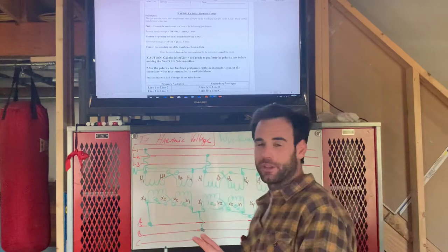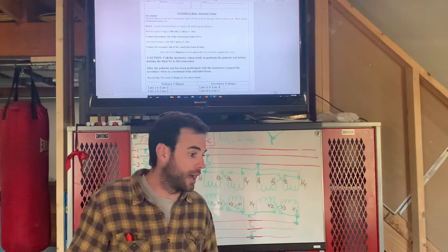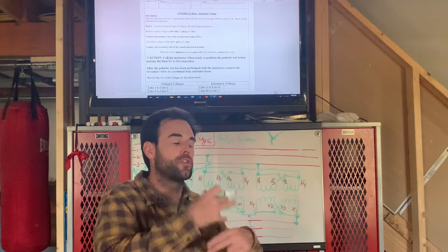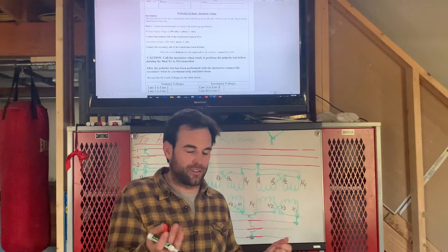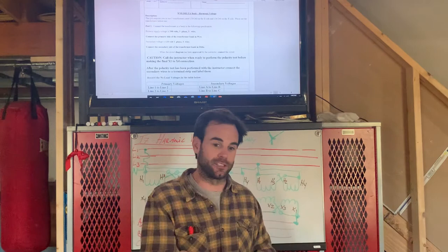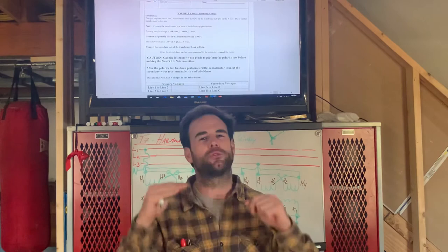Basically, for your passive filter, the power company would come to your house, your commercial establishment, your industrial establishment. What type of loads do you have? What are you starting up at what time? And they would size this passive filter for those specific loads. All that would happen is that passive filter would just induce a signal, the complete opposite polarity as the harmonic, to cancel it out. Passive filters are more or less for when you have the same loads turning on at the same time all the time. So they can design something specifically for that.